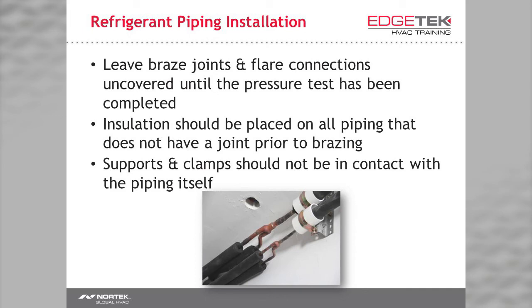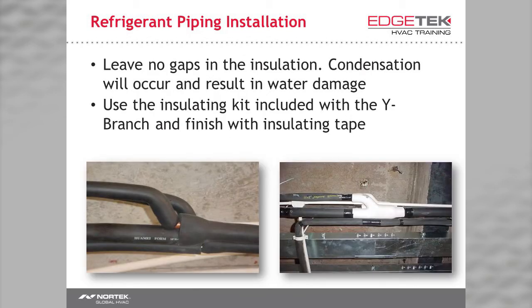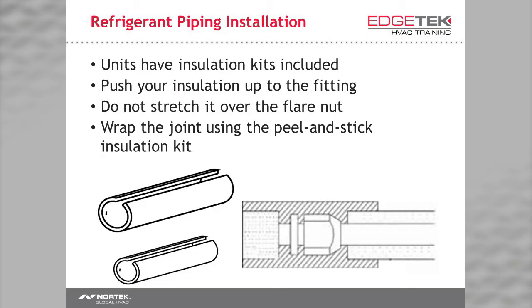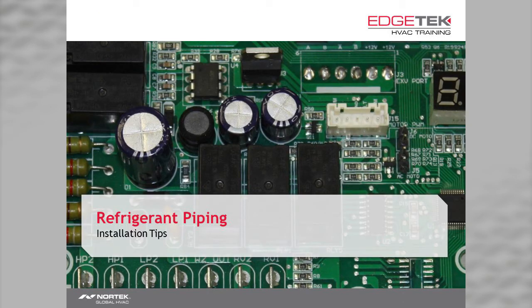Leave those off and leave your flares and other joints exposed until a pressure test has been completed successfully. Any leaks are much easier to find that way. When finishing the insulation, leave no gaps. You do not want condensation ruining drywall or ceiling tiles. With every indoor unit, we have peel and stick insulation wraps large enough to go around your insulation and flare nuts. So let's discuss some hints we've gotten from folks in the field.